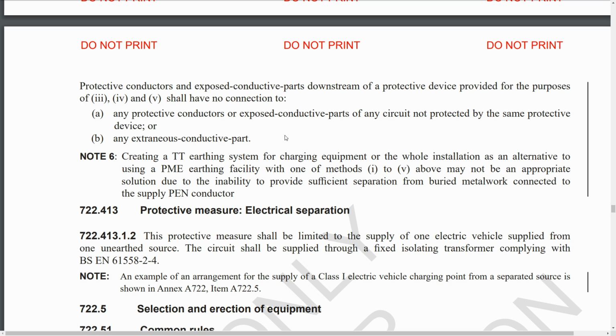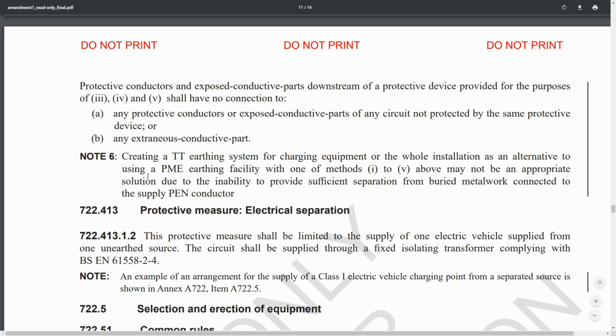Now this isn't going to be particularly difficult to do because in most cases the devices mentioned are going to be integrated into the charging point. So you just have the charging box on the wall, and that's where the device is, and all it's covering is literally the charging lead coming out that you would plug into the vehicle. But there might be some really vague things where if you've got, say, the thing rather than the charging equipment, it was in the building somewhere, you can't have any connections between anything from that point onwards to any other circuits or exposed conductive parts or whatever. So things like supplementary bonding from the protective conductor there to, say, a nearby water pipe is not permitted because that's obviously a connection to some other conductive part there. Not particularly likely, but it has been mentioned there.